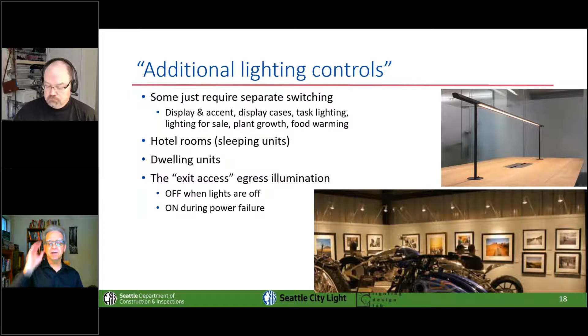That last one causes a lot of confusion. What the building code calls the exit access is everything between where you're standing or sitting at your desk and the stairwell door or the door to the outside. That whole pathway needs to be lit in an emergency. The old school way to deal with this was to leave about one light out of every six or so lit 24/7 forever—they'd have to replace those twice as often. But now code says those emergency lights have to turn off when the general lighting turns off, and only come on if there's an alarm or a power loss.